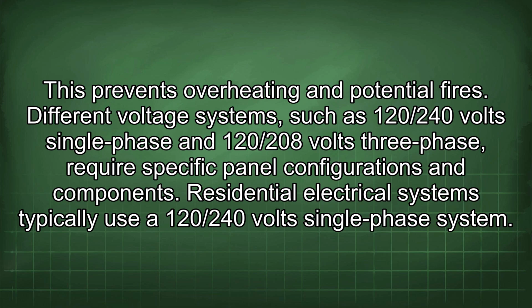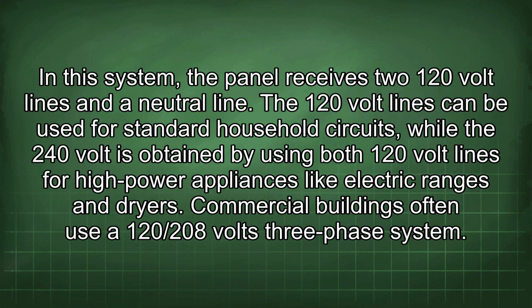Different voltage systems, such as 120/240 volts single-phase and 120/208 volts three-phase, require specific panel configurations and components. Residential electrical systems typically use a 120/240 volts single-phase system. In this system, the panel receives two 120-volt lines and a neutral line. The 120-volt lines can be used for standard household circuits, while the 240 volts is obtained by using both 120-volt lines for high-power appliances like electric ranges and dryers.